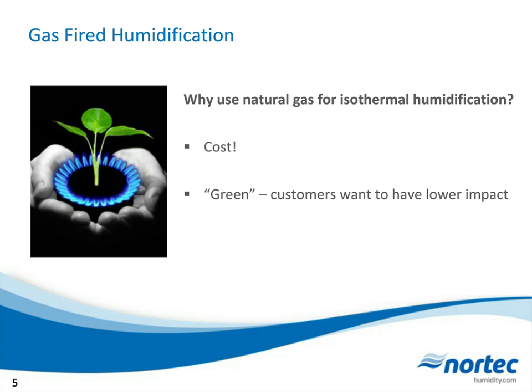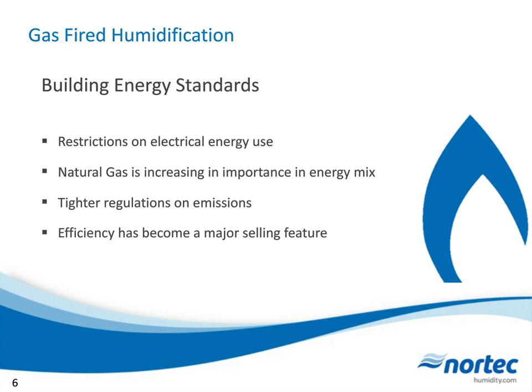More reasons to use gas: there are restrictions on building energy use, including building electricity demand. What we're seeing is restrictions on how many kilowatts a building can demand per month. If you're using electric humidification, you might exceed your allowed demand, whereas natural gas humidifiers obviously have less electrical demand.